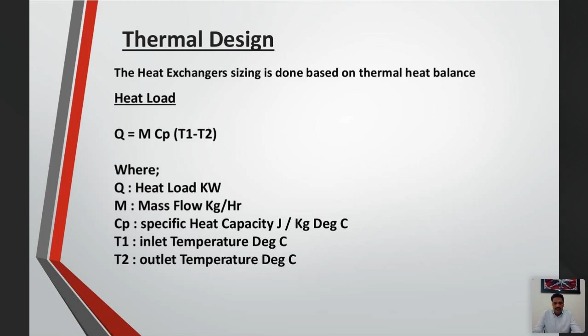Once you find out the heat load, you have to find out the heat transfer area. Heat transfer area is A equal to Q divided by U times LMTD. You may have heard this new term. What does LMTD mean? LMTD is the log mean temperature difference in degrees centigrade. U is the heat transfer coefficient. Once you get the heat load, you will come to know the heat transfer area.